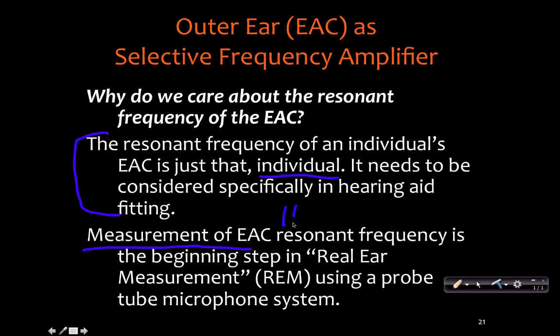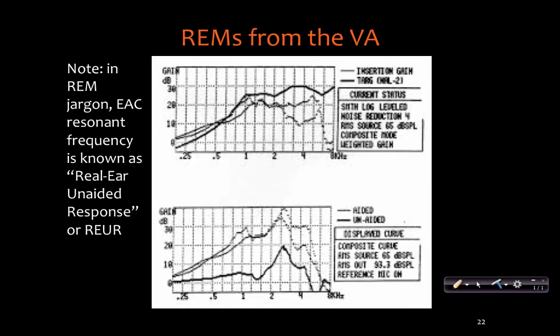in fitting hearing aids. So in hearing aid work, we would do a process called a hearing aid verification called real ear measurement, or REM, using a microphone that we stick down the ear canal right toward the tympanic membrane. So this is a very important part of high-level quality care provision of hearing aids, and really what should separate out audiologists from non-audiologist dispensers.